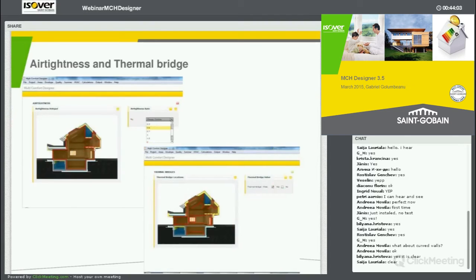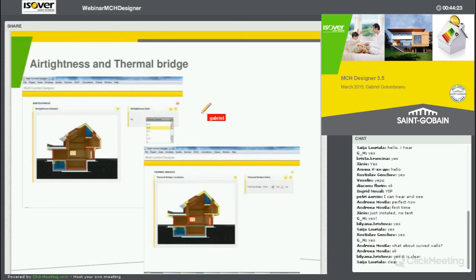The next part is linked to air tightness and to thermal bridges. This is even easier because you don't need to spend extensive time here. In the case of air tightness, it's a very simple page with a possibility to select different levels of air tightness. You are now in the design stage — you don't know where it is going to be — but you can propose: I would like to achieve an air tightness level of 0.6, which is more or less the limit from which you can say this building will perform in a good way.